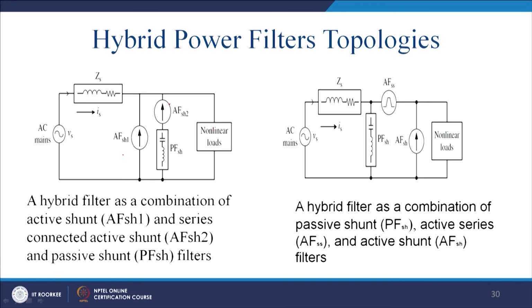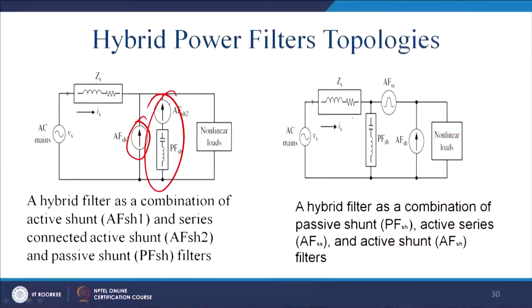Similarly, this combination has two shunts, mainly to reduce the effect of the harmonic currents. So here you have a shunt active filter, this is a shunt hybrid filter, and both are placed so that this may be compensating the higher order harmonics, and this is for compensating the lower order harmonics. Same way you can have, as I was telling, passive shunt first, then active shunt, with the series in between.